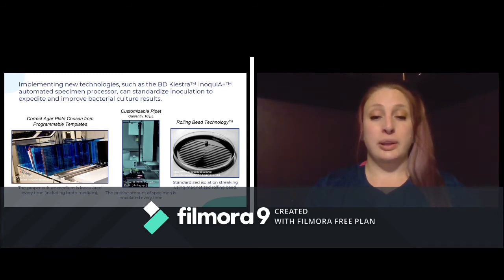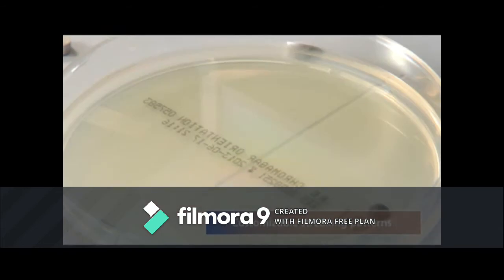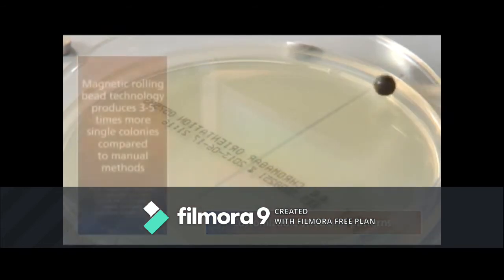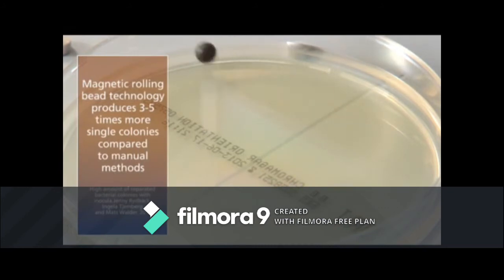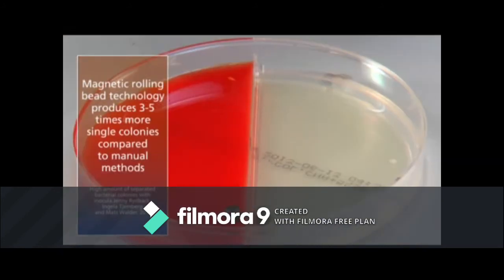The proper culture medium is inoculated every time, and this also includes broth medium. The precise amount of specimen is inoculated every time, and this is also customizable. For the proposal research I did, I used 10 microliters. And there's also a standardized isolation and streaking method that was patented by BD. It's called the rolling bead technology, and it is a magnetic bead which rolls across the surface of the agar, and it pulls the specimen in an even distribution around the plate.